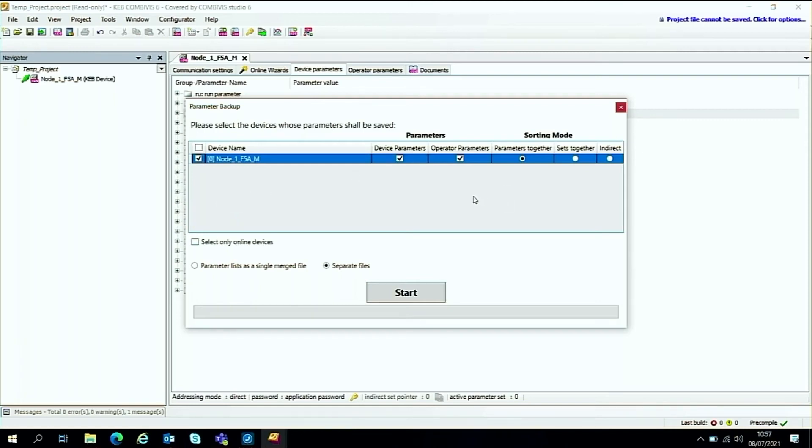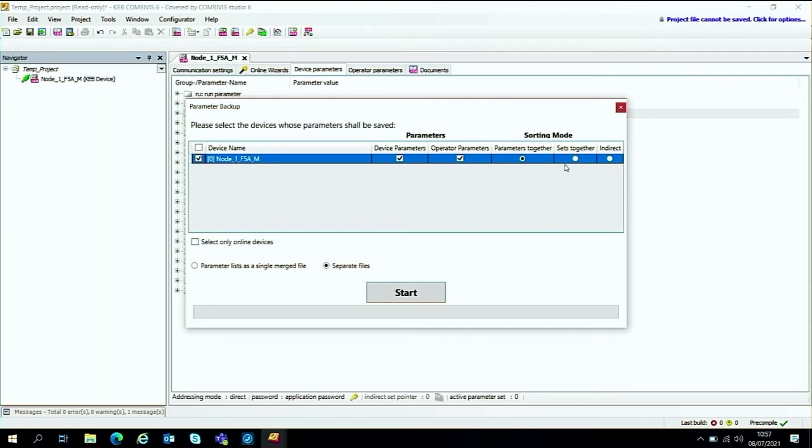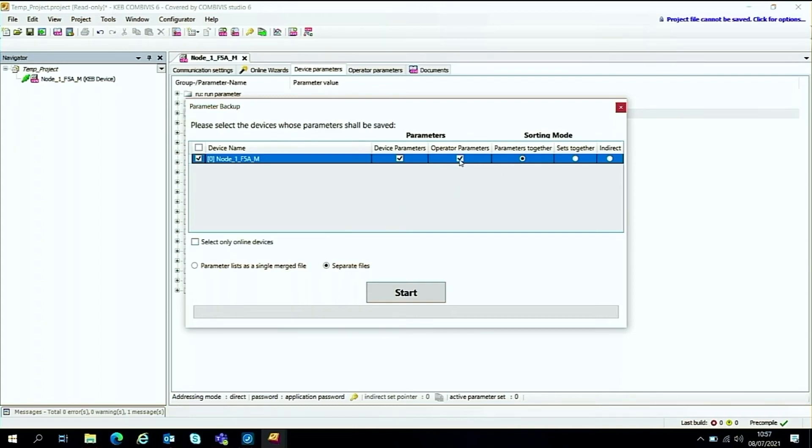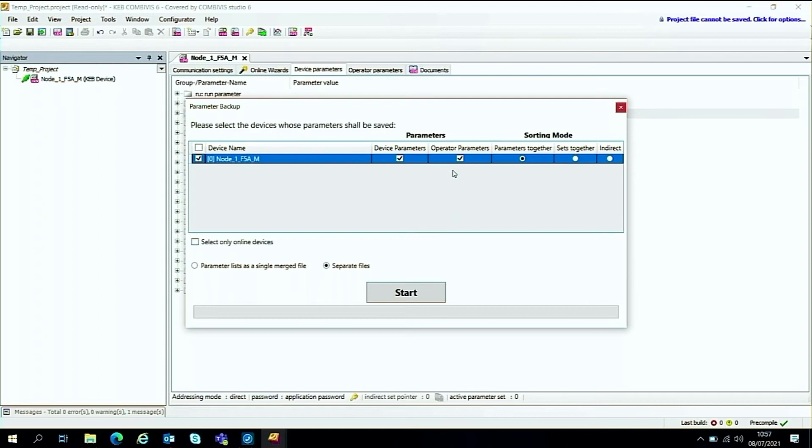Also it gives you a few options on this, where you can do the backup the device parameters or the operator parameters and a few other options there. If it's just a standard serial communications, I suggest there's no need to backup the operator parameters. But if you have a field bus, ProfiNet, ProfiBus, EtherCAT, these sort of ones, it may be worth backing up the operator parameters as well. So for the sake of this quick demonstration, I'm going to disable the operator parameter backup. And once you've done that, it's a case of press the start button down here, click on the start button.